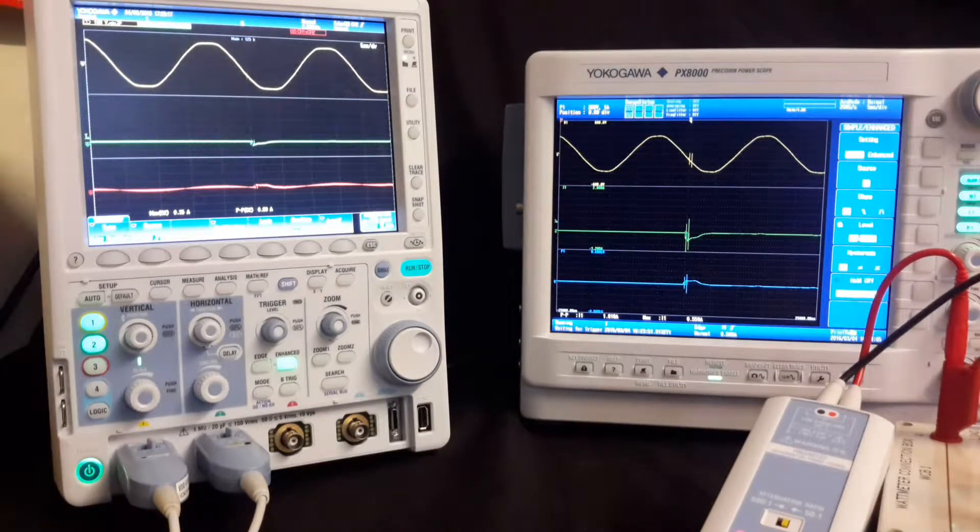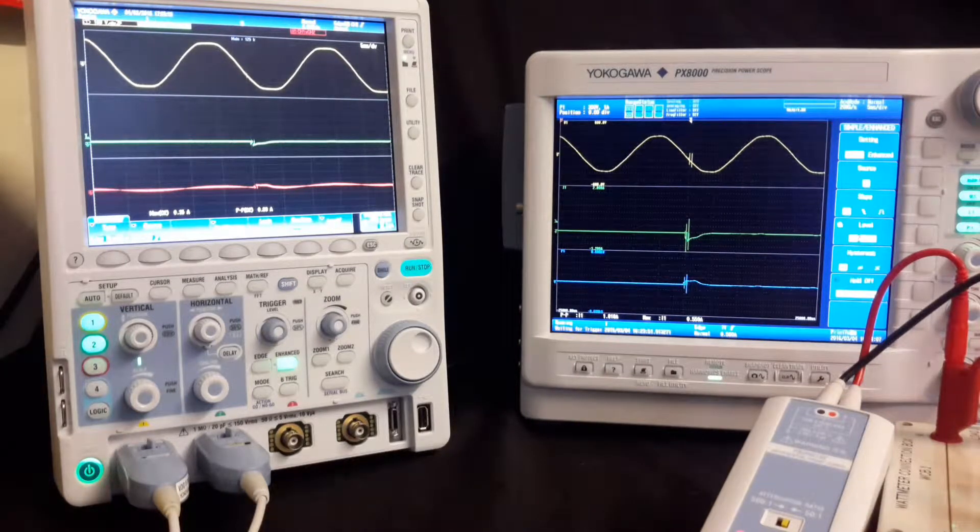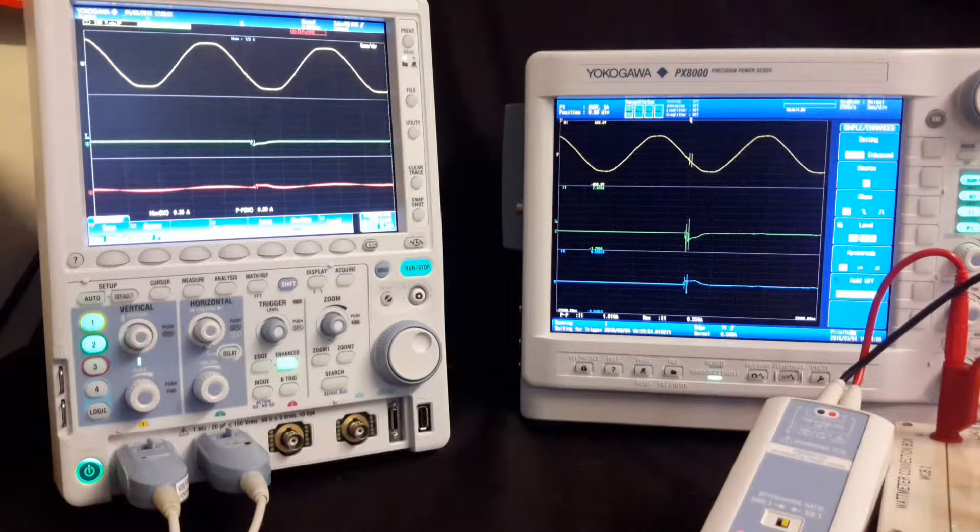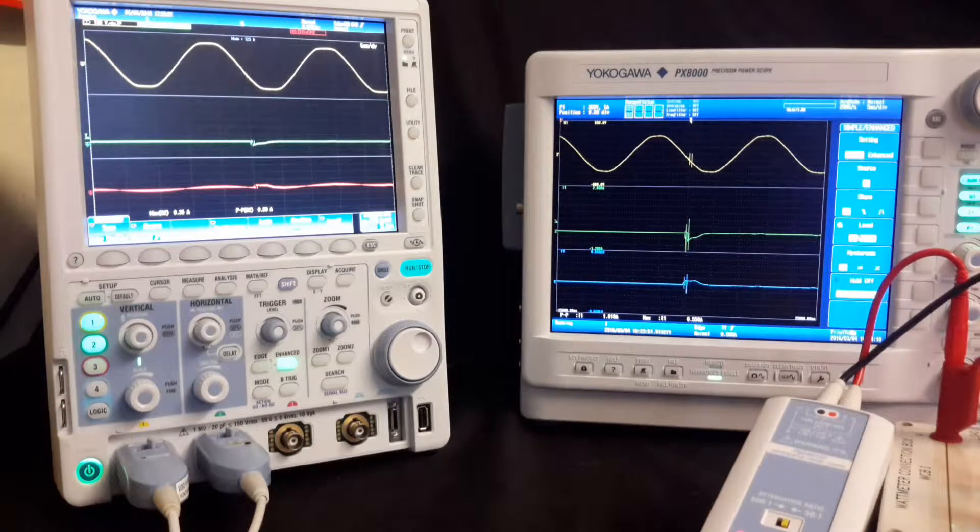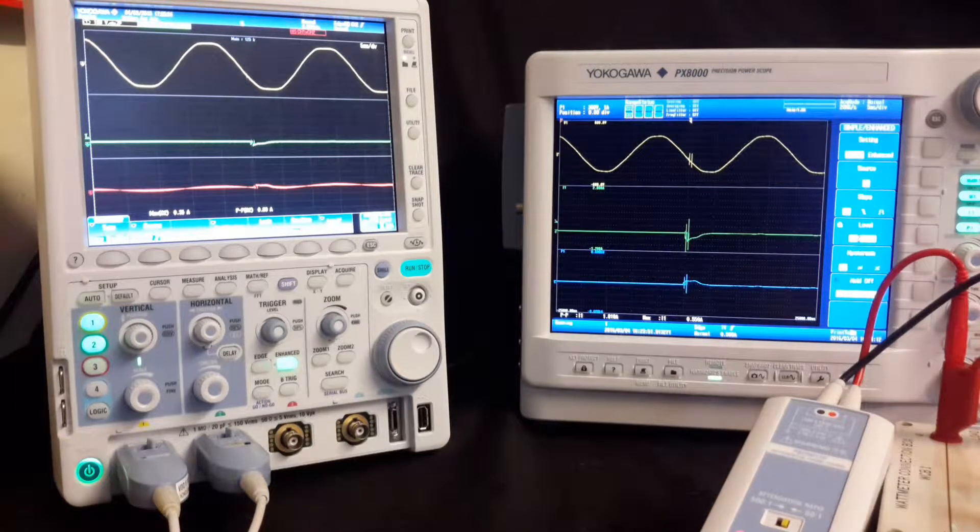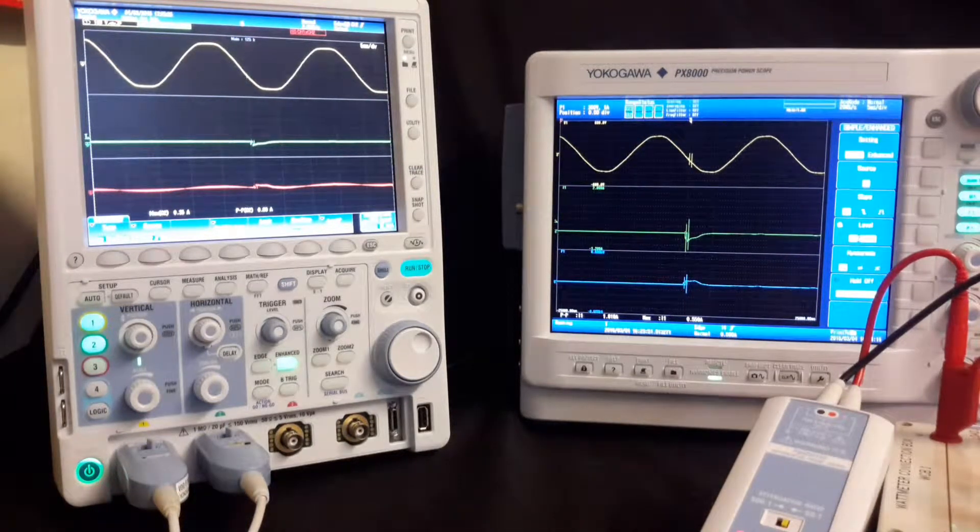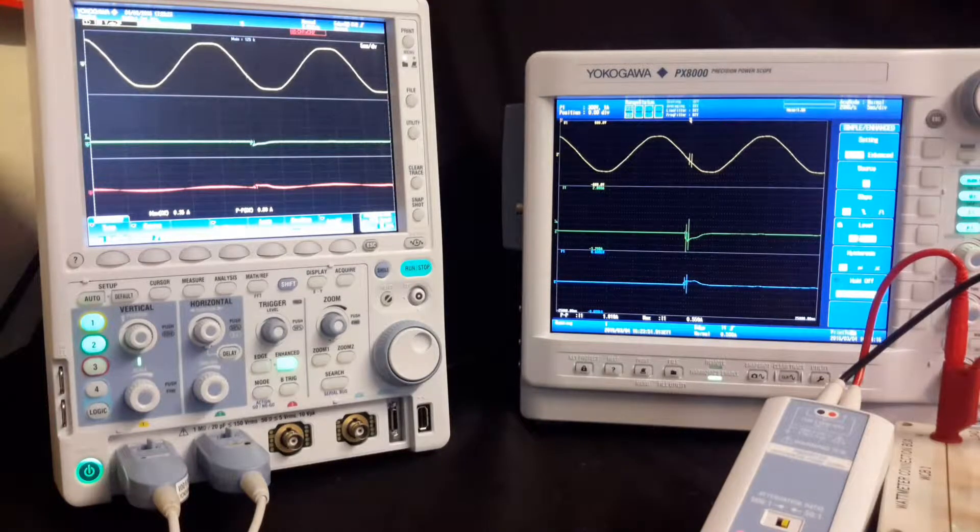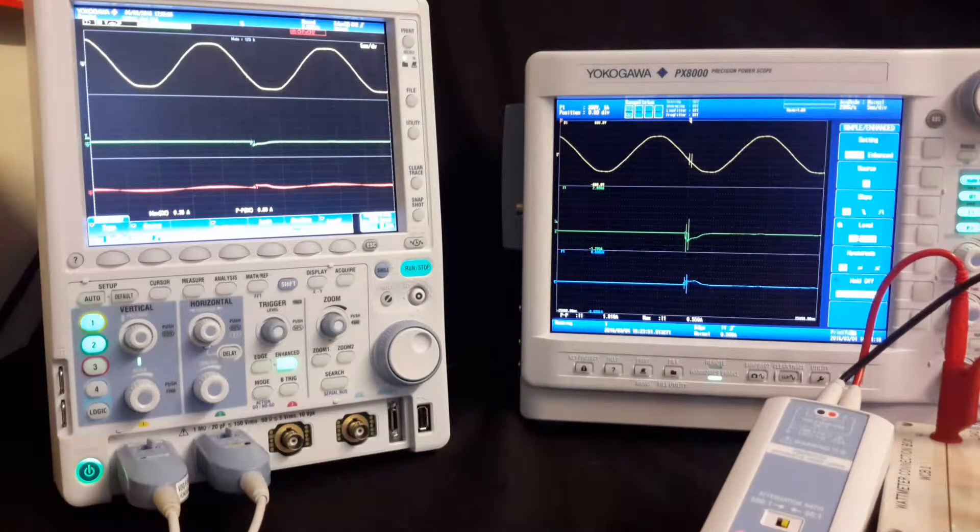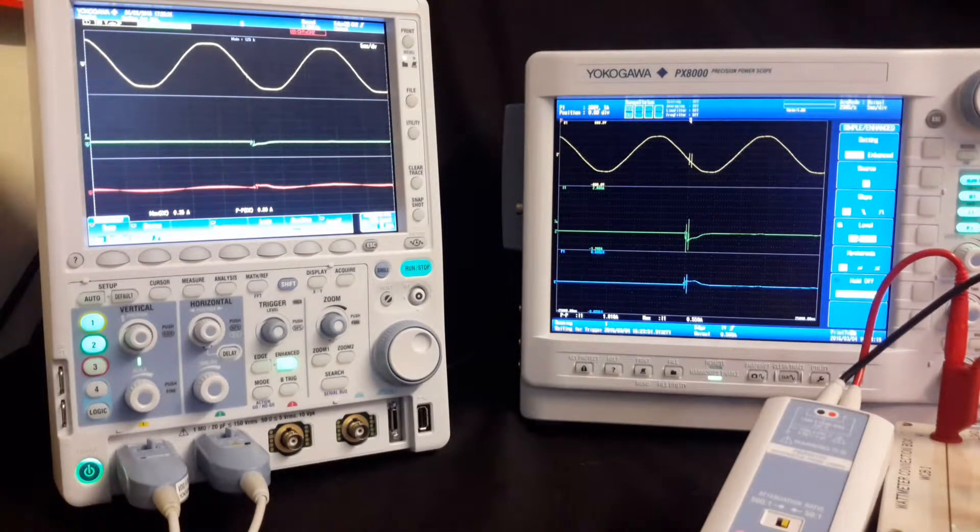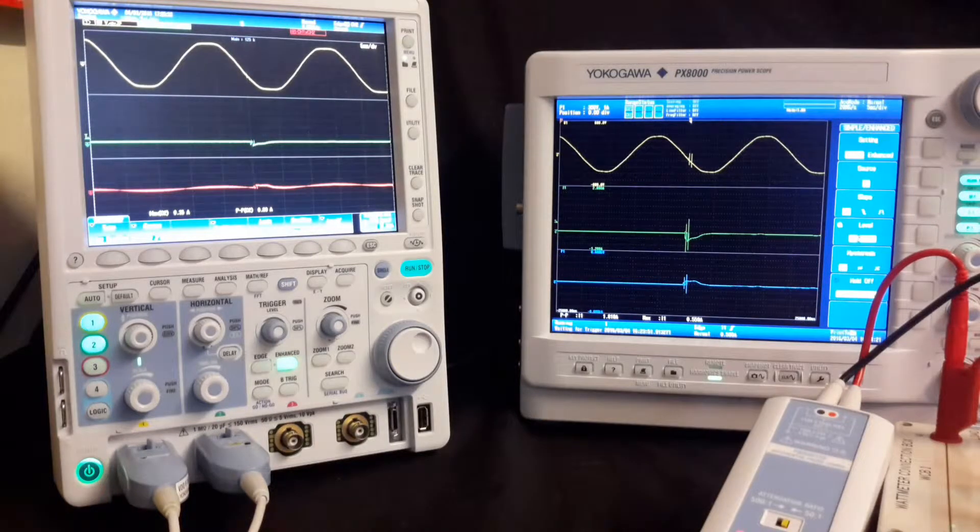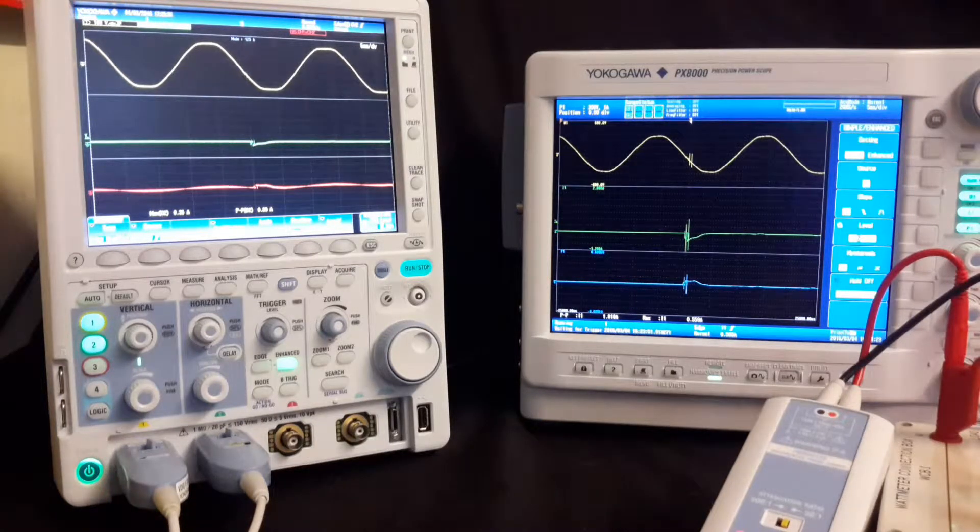Just to explain the displays, both the top lines represent the voltage. The center lines represent the current. The bottom line on the oscilloscope represents a multiplication of voltage and current, that's channel 1 and channel 2. On the PX8000, this is a true power measurement.